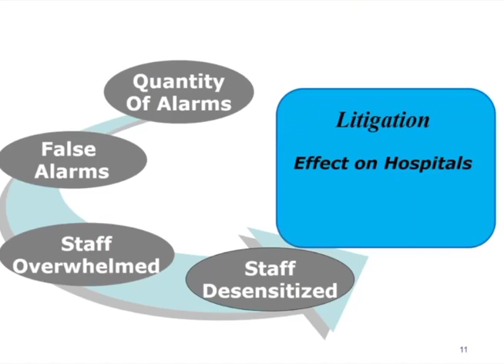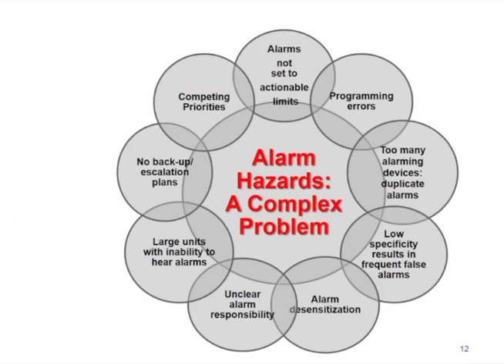Alarm hazards, as you can see here, are quite complex. Missed alarms and bad outcomes may result from a combination of many different things, such as not setting alarm limits properly, programming errors, too many alarming devices, low specificity resulting in frequent false alarms which desensitize the staff, unclear alarm responsibility by staff, large units with the inability to hear alarms, especially with room doors closed and no backup plan for alarm escalation, and competing staff priorities, because we all know that staff have many, many important things to do besides address alarms.